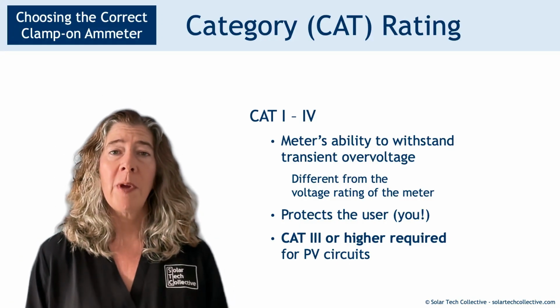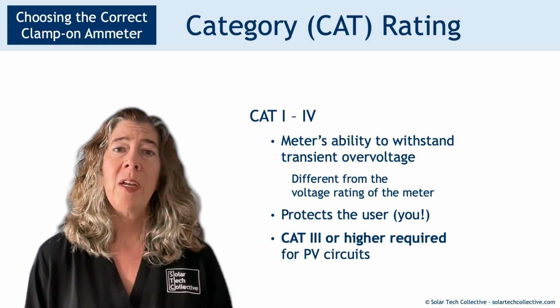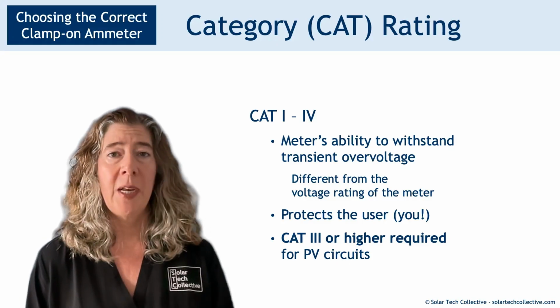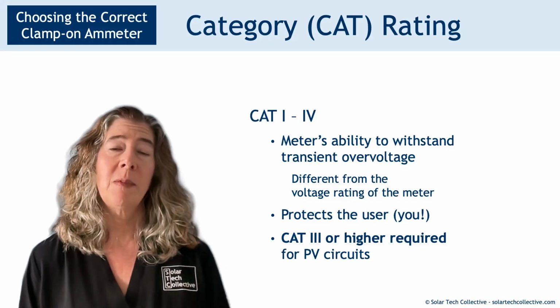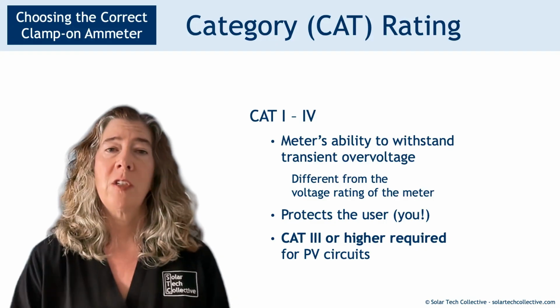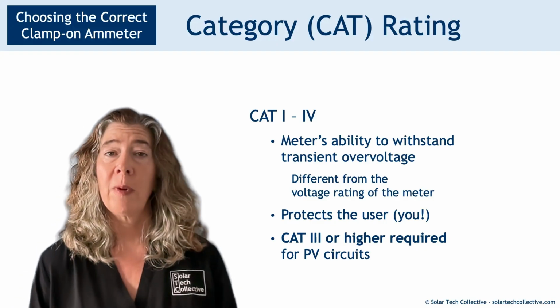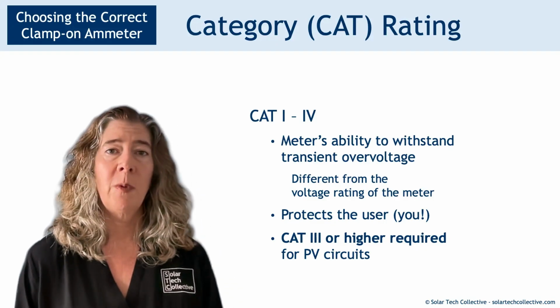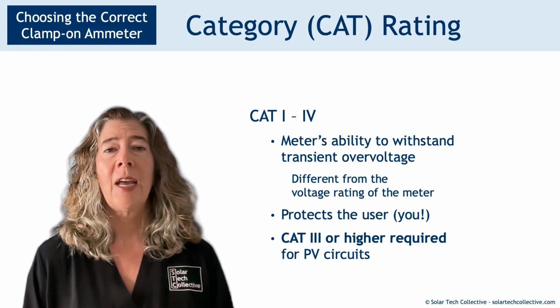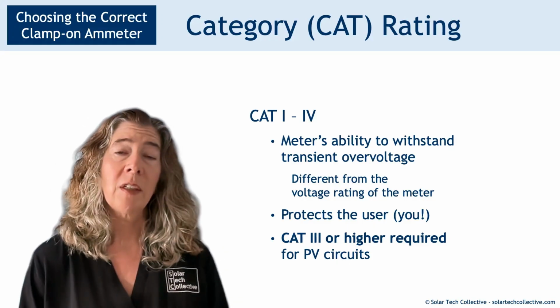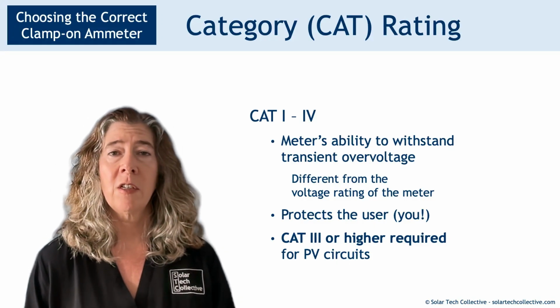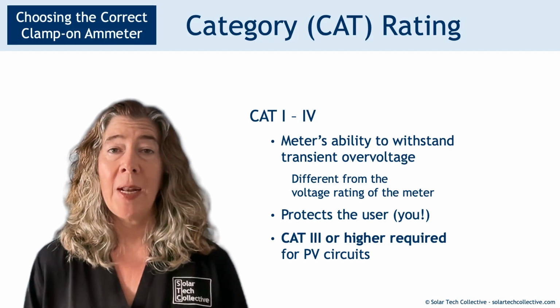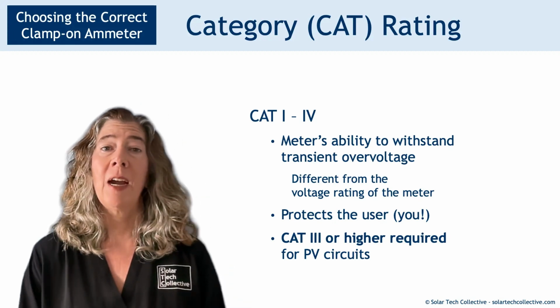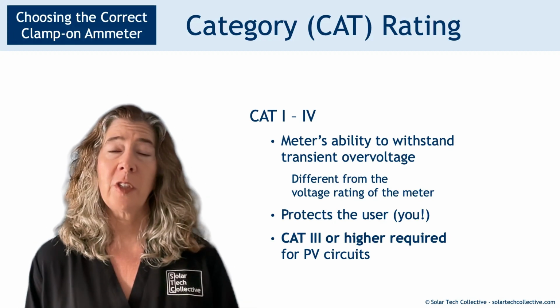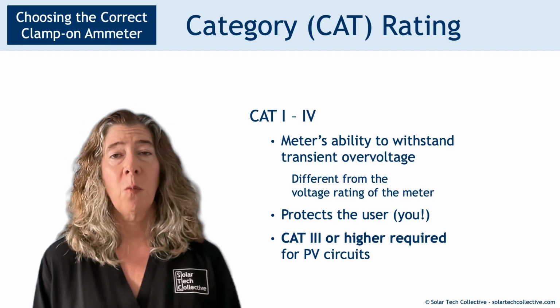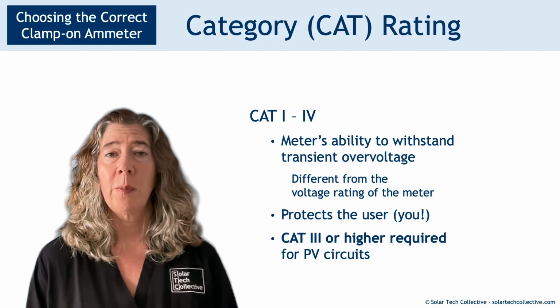For PV circuit measurements, we need to have a CAT 3 or higher rated meter. There is an IEC standard 61730-1, which defines PV circuits as category 3 for these purposes. They are distribution or fixed installation conductors. Category 4 applies to things like utility and service entrance conductors. If you have a CAT 4 rated meter, that's a higher rating, it has a higher withstand value, that's perfectly acceptable to use, but you shouldn't be using a CAT 1 or 2 rated meter to measure PV circuits.